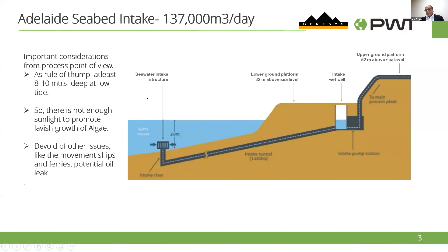This is the Adelaide seabed intake — a 137,000 cubic meters per day plant. The depth of the seawater is about 14 meters, and it's about 1.4 kilometers from shore. As a rule of thumb, in a seawater intake system, the intake should be at least 8 to 10 meters deep at low tide. This is required because at that depth sunlight is minimal, so you avoid lavish growth of algae. You also need to ensure the intake is not near ferry routes where oil spills can occur, because oil is a killer for a membrane.